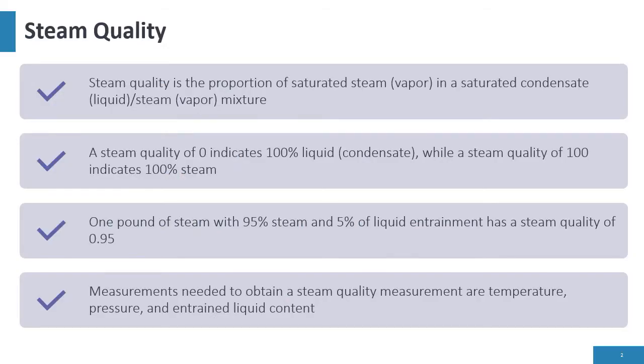Steam quality — what is steam quality? It's the proportion of saturated steam vapor in a saturated condensate liquid-steam vapor mixture. A steam quality of zero indicates 100% liquid or condensate — it's all going to be water. A steam quality of 100 indicates 100% steam. That's what heat transfer is designed for: 100% steam quality, which is the correct amount of latent energy (BTU per pound) and sensible energy (BTU per pound) of the vapor at a given pressure.